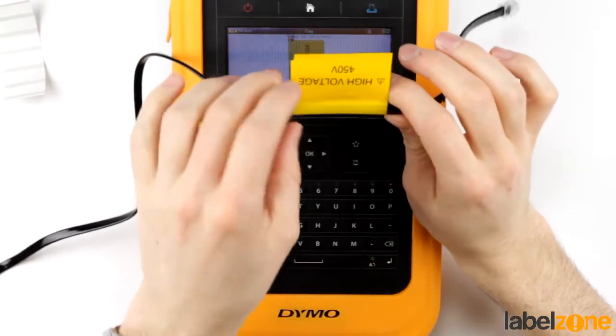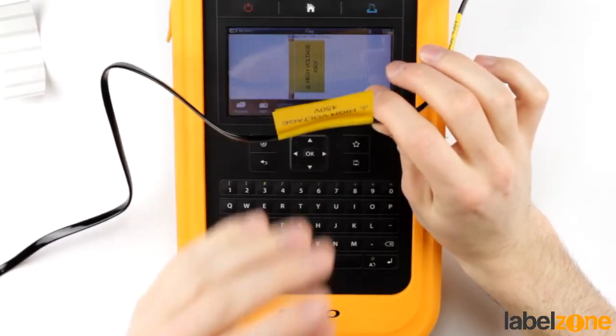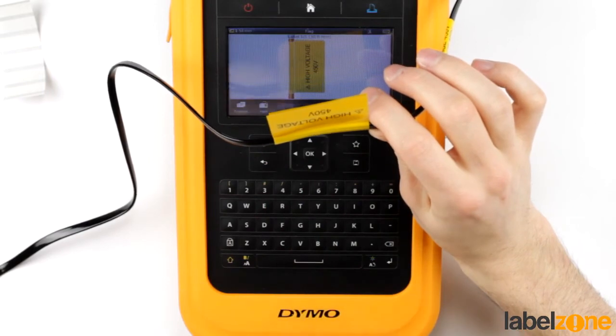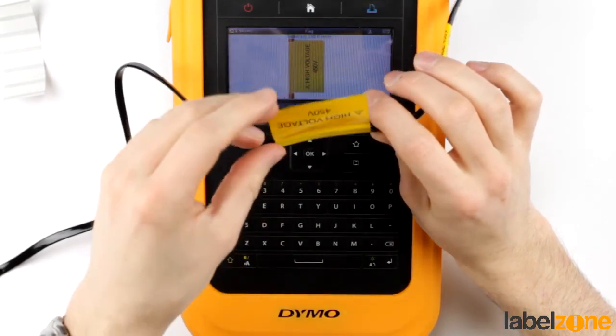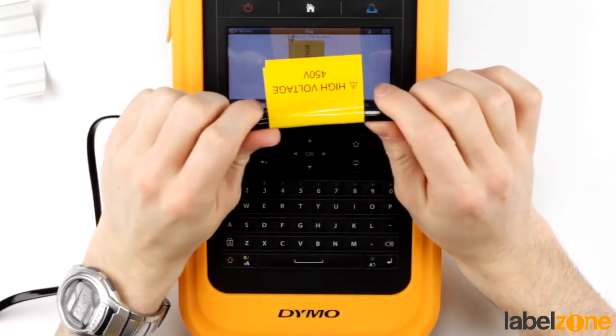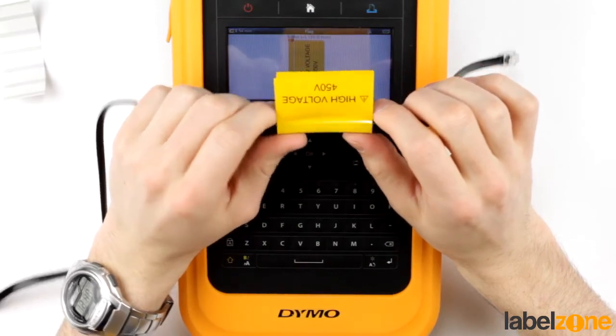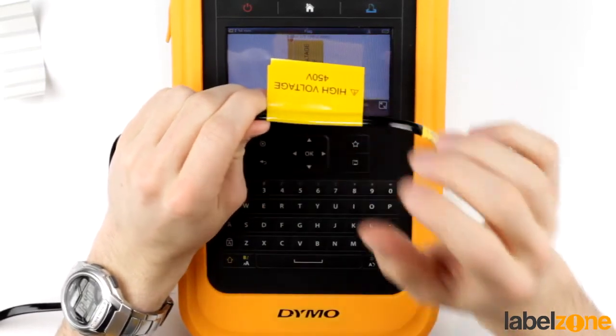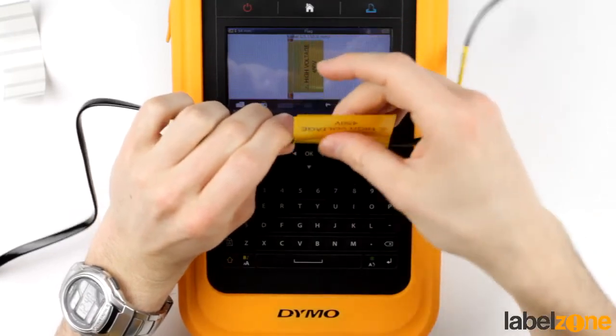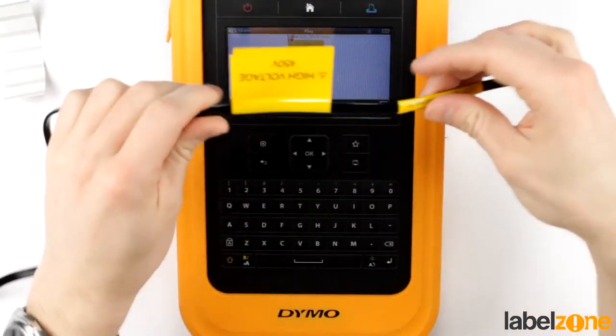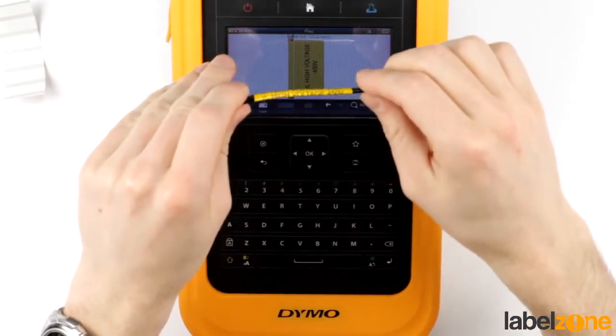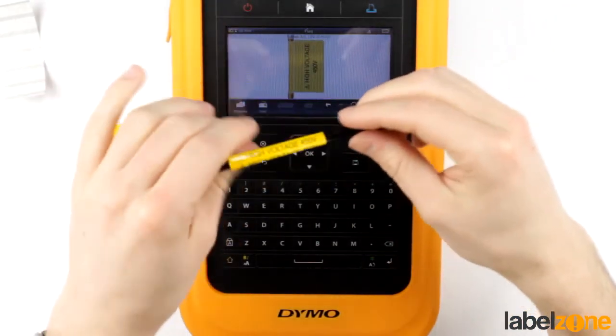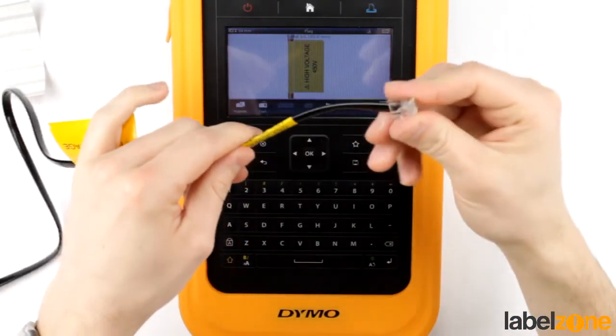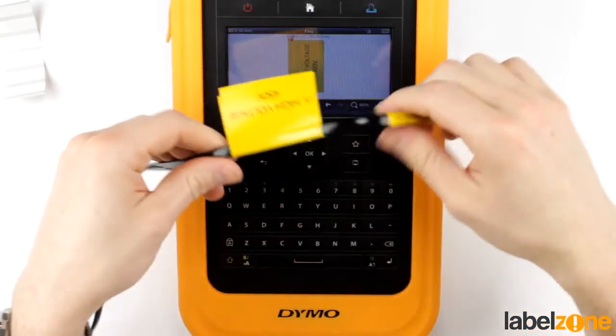You probably wouldn't use this in a data center. Flag labels will have an effect on airflow, so in racks or server racks or data cabinets, airflow is essential to keep the equipment cool. Flags could have an impact on that. It would be recommended to use the wire wraps, or even heat shrink if you're going to be terminating the end of the cable yourself.